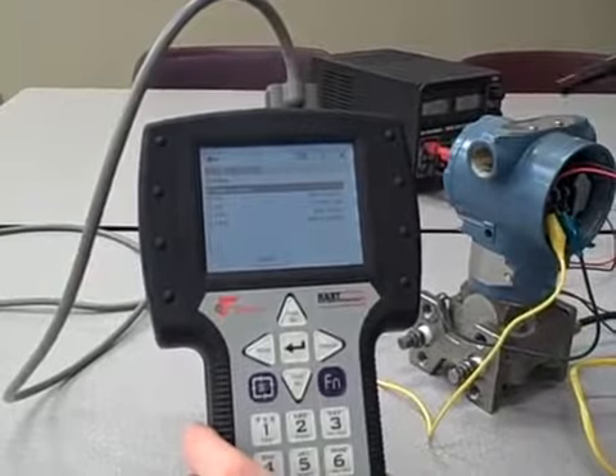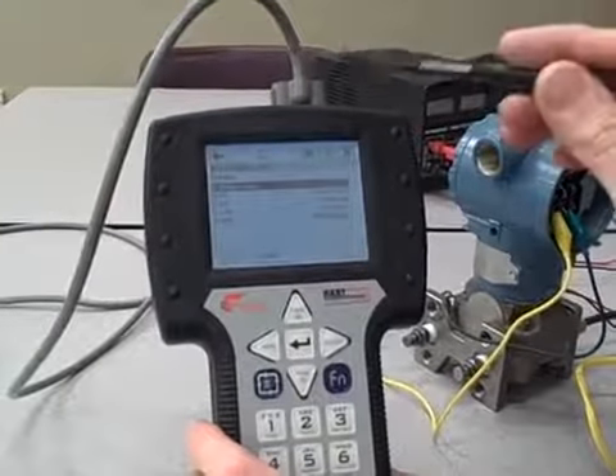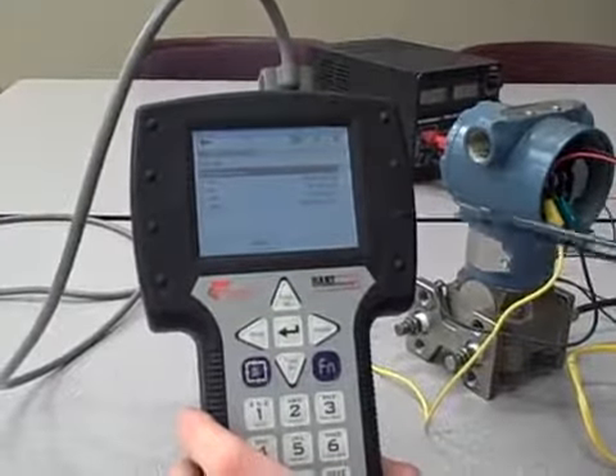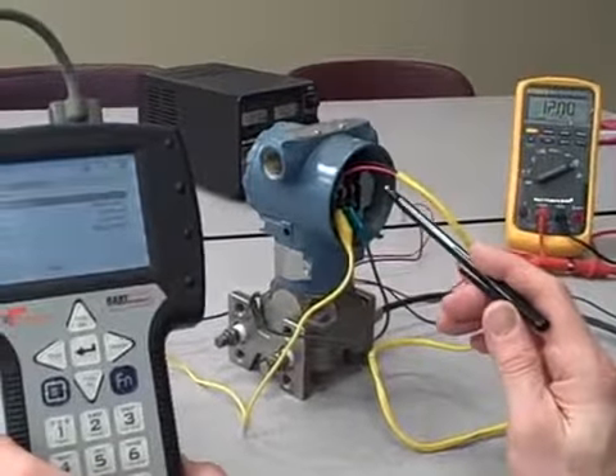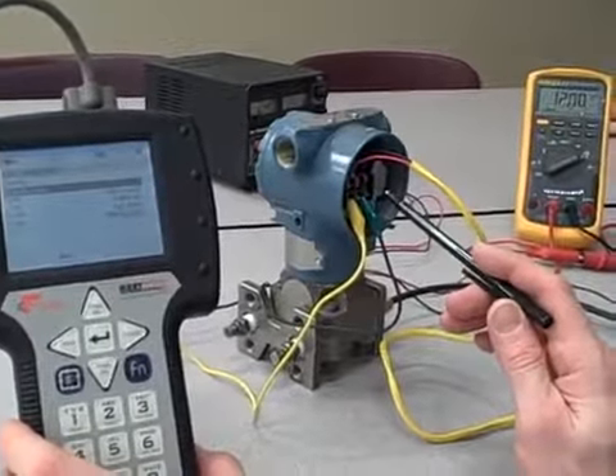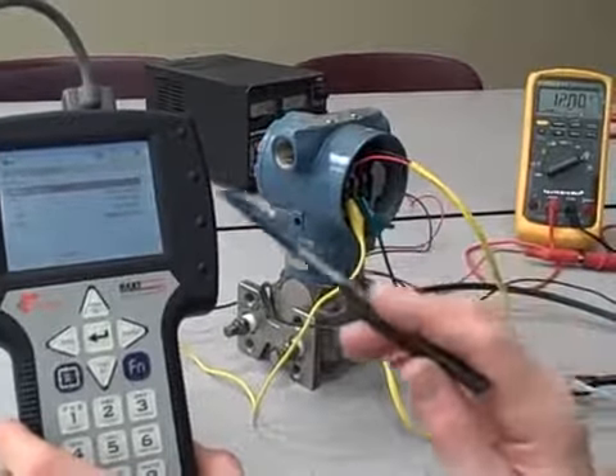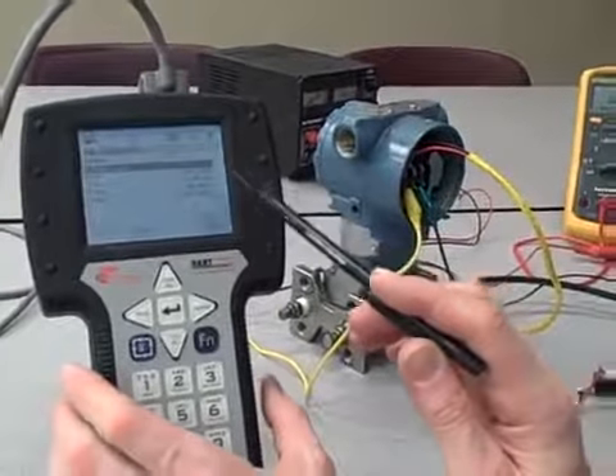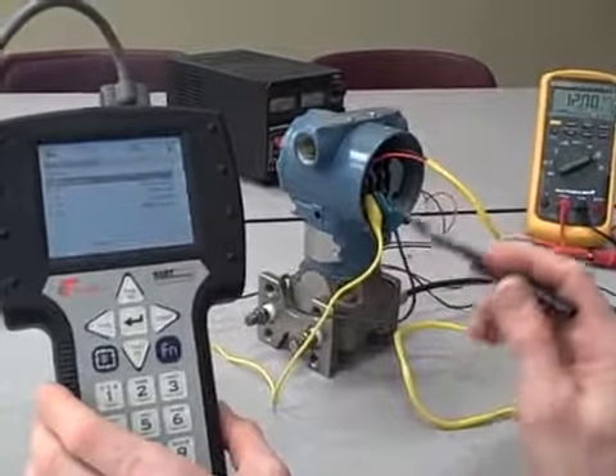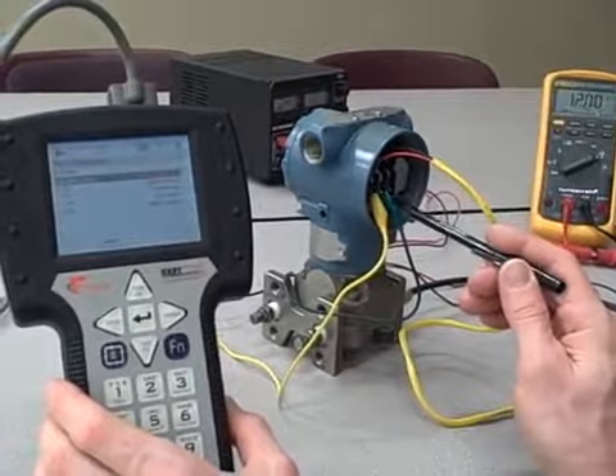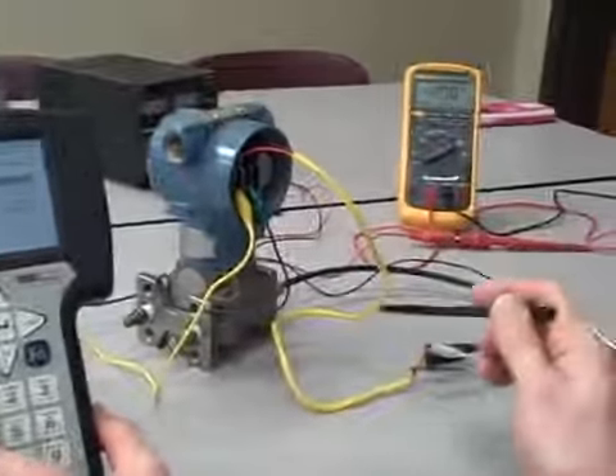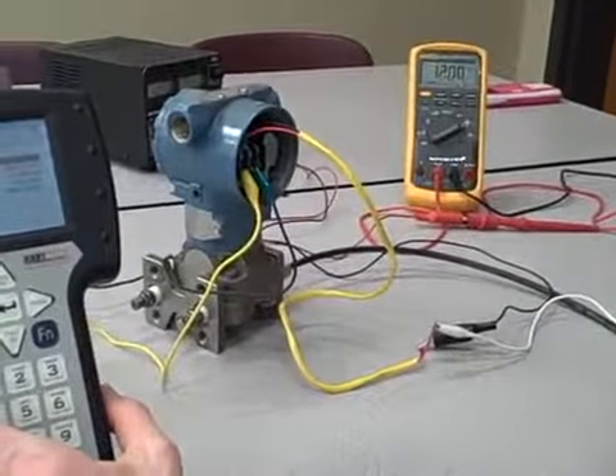But remember, this communicates using pulses of AC voltage and current superimposed on the same two wires that the DC 4 to 20 milliamp signal goes through. And I can attach this communicator to the transmitter directly in parallel with the transmitter or anywhere in parallel along the signal cable leading back to the power source.